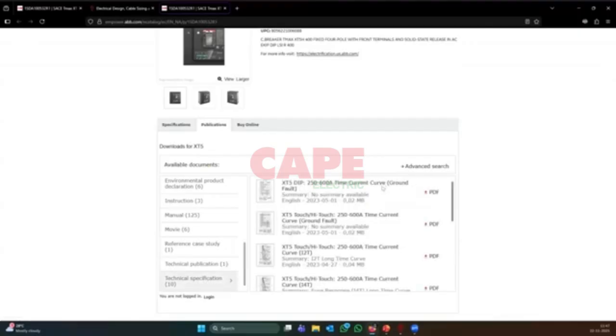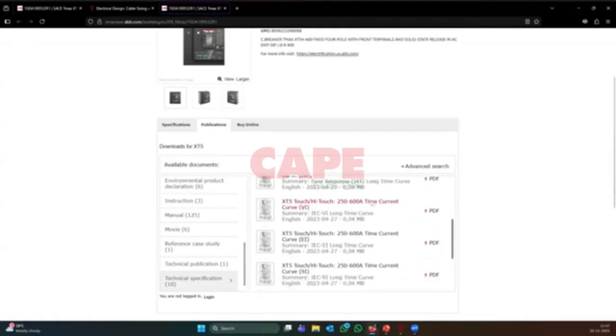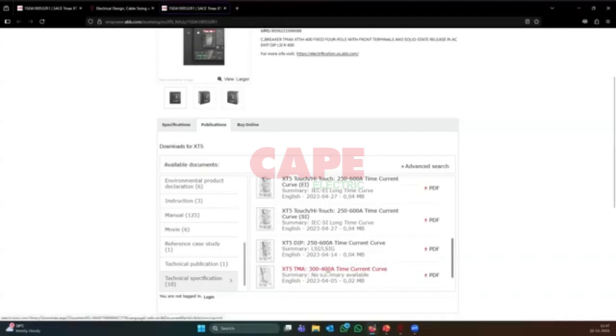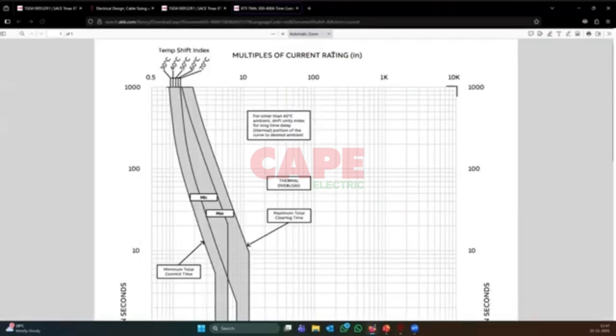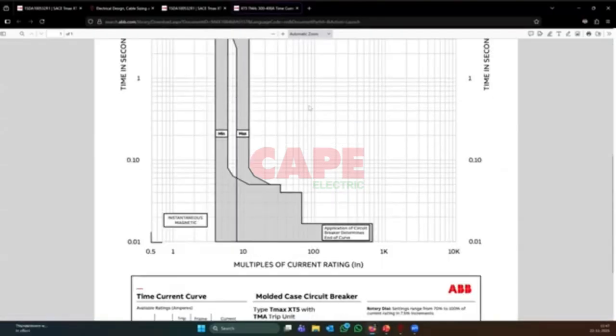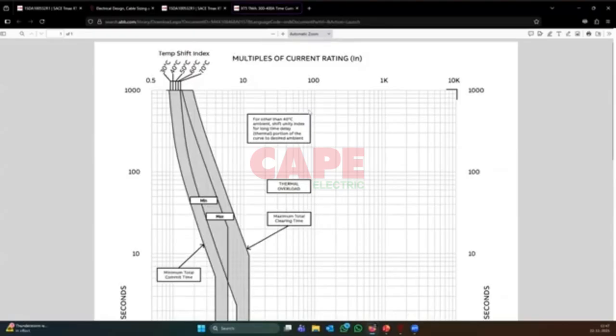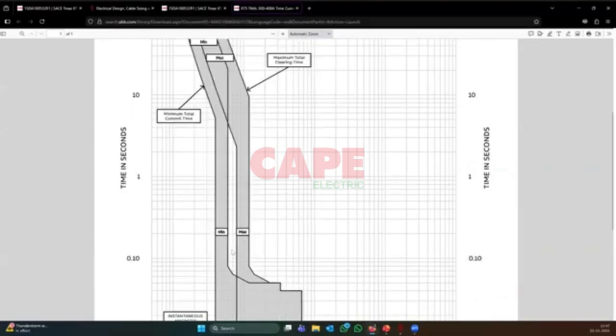Suppose I want to go with something around 400 amps. Just go a little bit down, and you have 300 to 400 amps. There is a time current curve, so I just click it and it opens. In this, they have given the tripping characteristics, the tripping curve. Now the problem is I have to check what is the setting of the MCCB I want to keep. Sometimes you will need to change the settings.